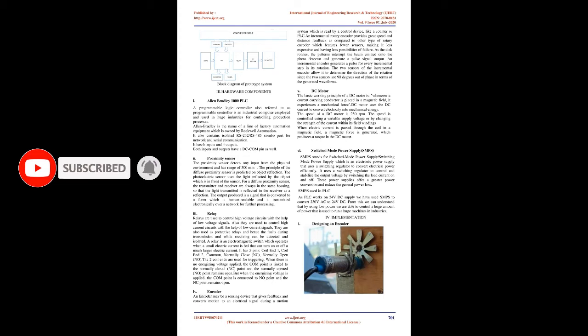A relay is connected to the PLC, which is used to control high current circuits using low current signals. When a 12V supply is given from the battery, further connected to a motor, the motor generates back EMF which may damage the PLC. Hence a relay is used between the motor and PLC. To count the number of objects passed through the conveyor, an encoder is used which gives output in the form of pulses. It has a disc which rotates and generates a pulse for each incremental step in its rotation. When the predefined number of objects passed through the conveyor is the same as that received at the destination point, an indicator light is turned on.